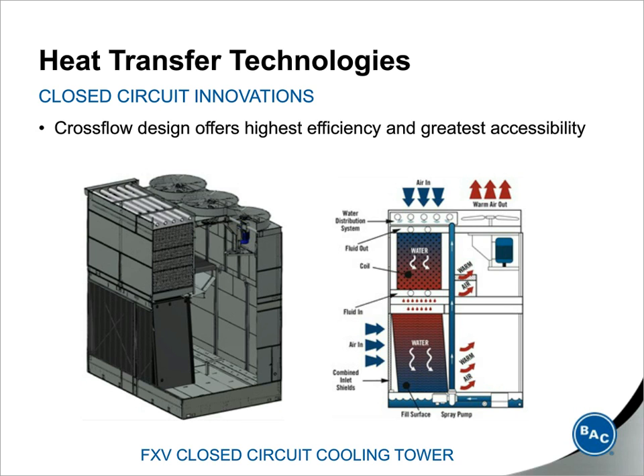And I don't go into crossflow versus counterflow too much in this presentation, but one of the great benefits of the crossflow design is accessibility, because you have an area where you can access the collection basin, the distribution basins, and the drives, which are essential to unit operation. Now, while counterflow closed-circuit cooling towers are a bit more difficult to maintain because they don't have as much accessibility, they can still be very useful when replacing existing counterflow units, or when there may be certain layout restrictions and a crossflow unit isn't ideal for that particular situation.